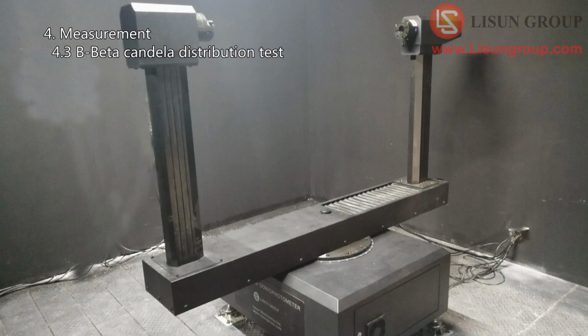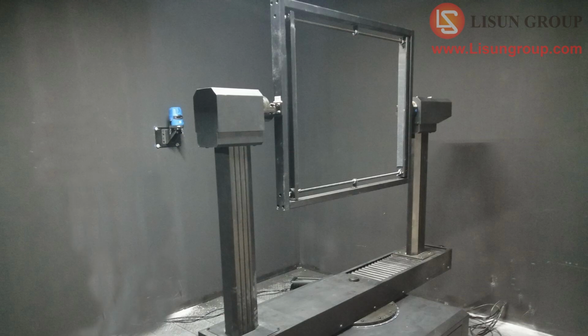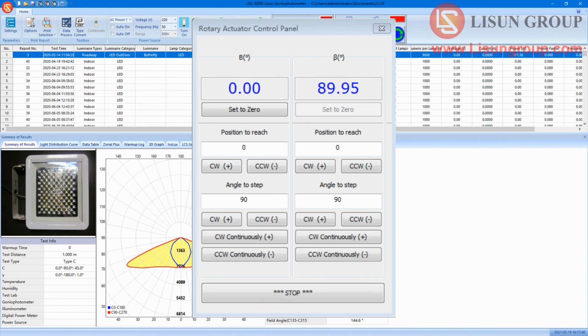The assistant arm needs to be installed back if you do the B-beta test for floodlight. Then install the B-beta clamp to the goniophotometer. Make sure it's vertical. Click Type Convert to change the angle to B-beta. Click Rotary Actuator Control Panel. Rotate both B and beta angles to the 0° position.